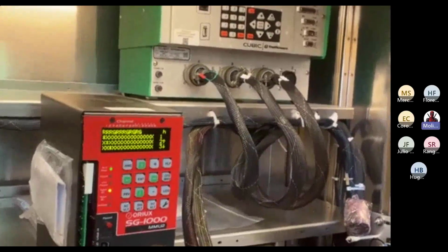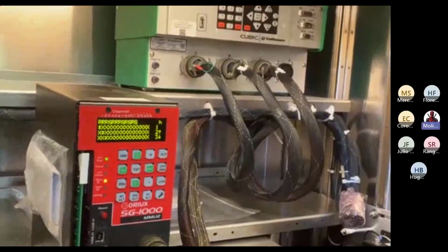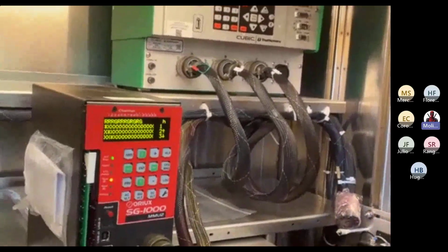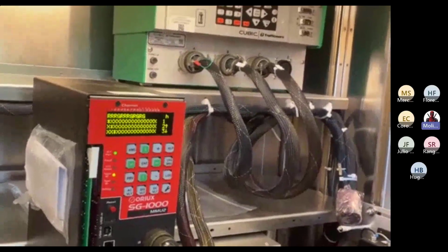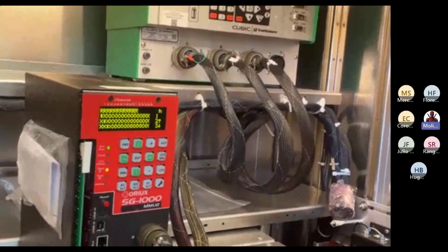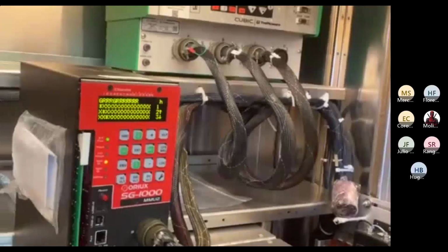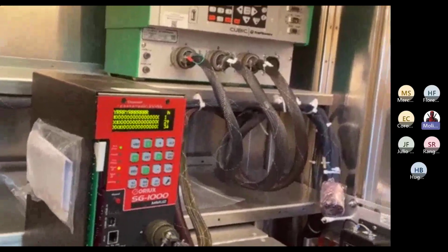No. The monitor is, for lack of a better word, dumb. It's just monitoring things; you tell it exactly what to look for, and it looks for those things and ignores everything else. Now our controller, when we get to that, will actually tell you, based on how you configured it, what jumpers you should have and what it's expecting. I can show you that. But the monitor is just reading off the card and showing you what it is, not what it should be.